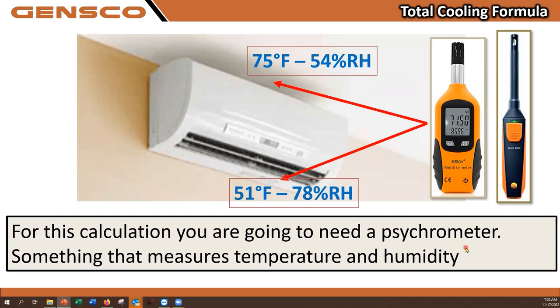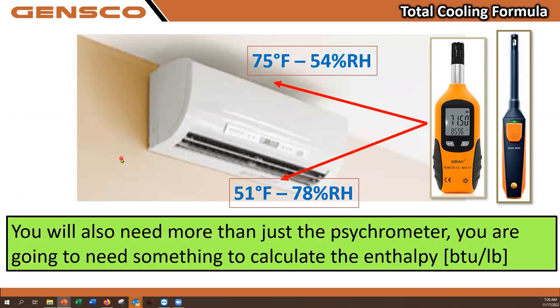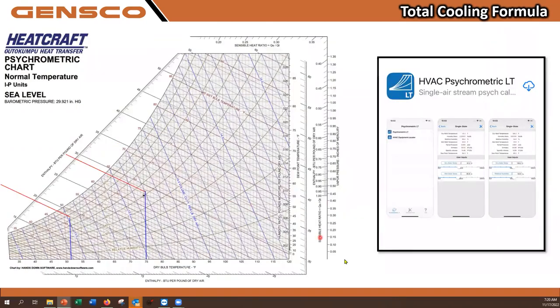So for this calculation, again, we're going to need a psychrometer. And we take these measurements: 75 degree, 54% relative humidity, 51 degrees, 78% relative humidity on the supply side. And we're going to have to use a couple more tools. That can either be a psychrometric chart you see on the left, or a psychrometric app on your smart device. Now I have both, but I prefer the app because it's really easy to use right there on my phone.